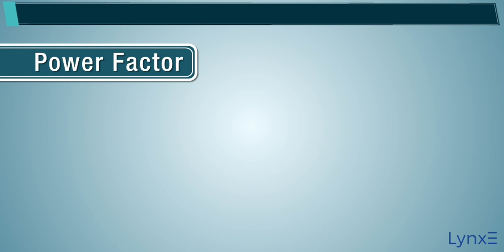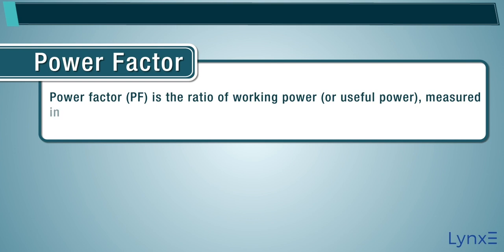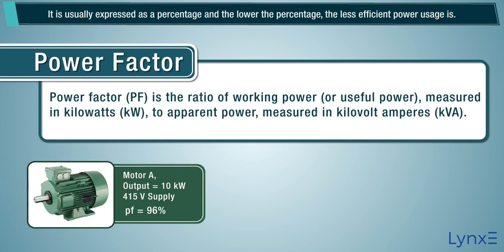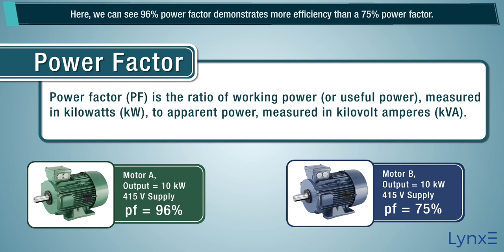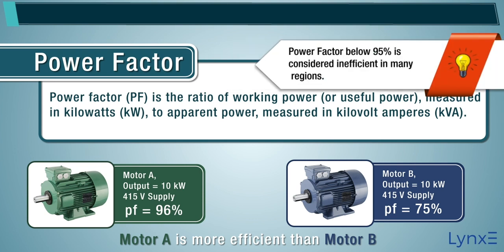Power Factor, PF, is the ratio of working power, or useful power, measured in kilowatts, to apparent power, measured in kilovolt amperes. It is usually expressed as a percentage, and the lower the percentage, the less efficient the power usage is. A 96% Power Factor demonstrates more efficiency than a 75% Power Factor. Note: Power Factor below 95% is considered inefficient in many regions.